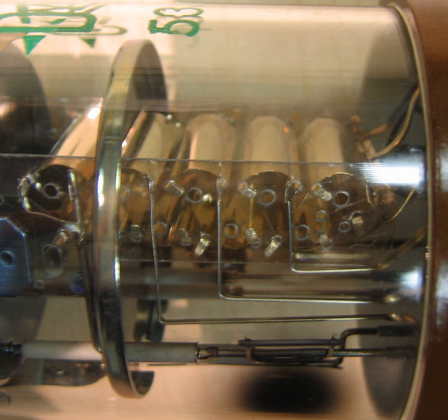Photomultipliers are used in numerous medical equipment designs. For example, blood analysis devices used by clinical medical laboratories, such as flow cytometers, utilize photomultipliers to determine the relative concentration of various components in blood samples, in combination with optical filters and incandescent lamps. An array of photomultipliers is used in a gamma camera. Photomultipliers are typically used as the detectors in flying-spot scanners.